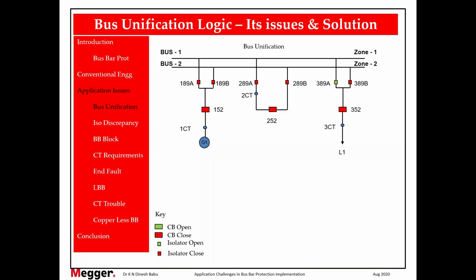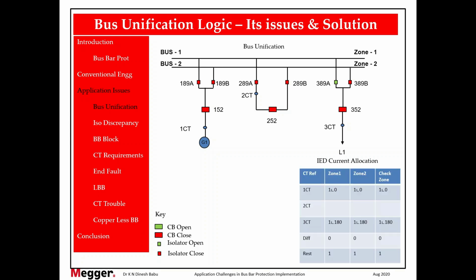Now you have 89A and 89B closed in one of the bays like this. This can be in any bay. Bay number 1 or bay number 40 or bay number 20, anything. If this happens, it is an issue and we have to address it. Now what is the issue? Let us see how we are going to address this. In the relay, we will follow this concept. The concept is very simple. Whenever any one of the bays has its 89A and 89B isolators closed simultaneously, the bus coupler CT will not be read in any of the zones. This is the concept. Now why should we eliminate it?